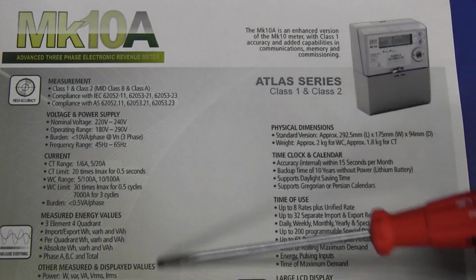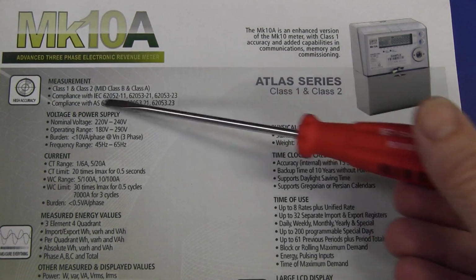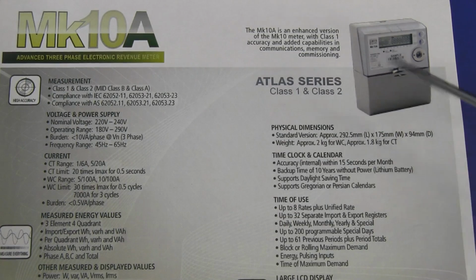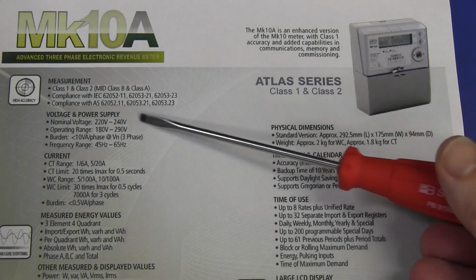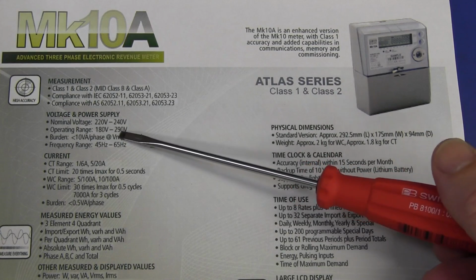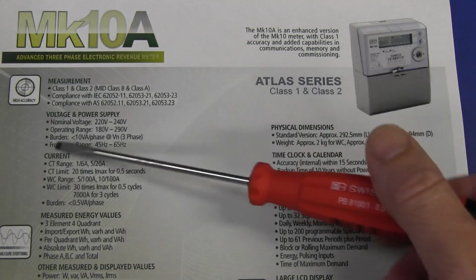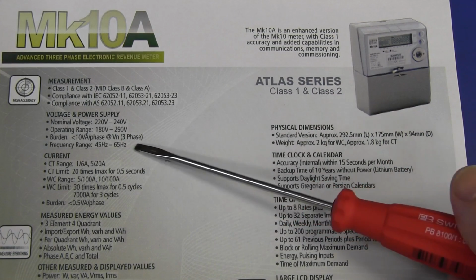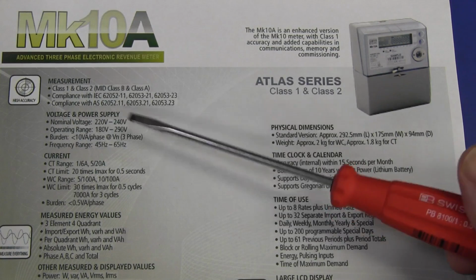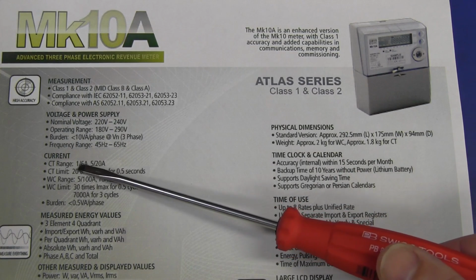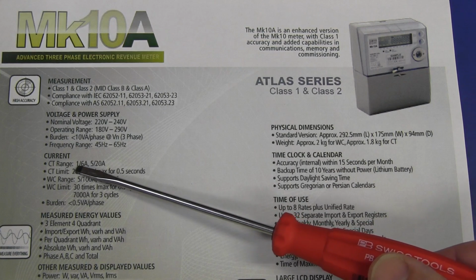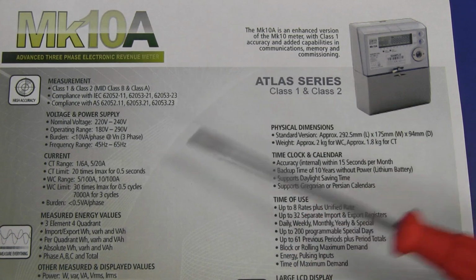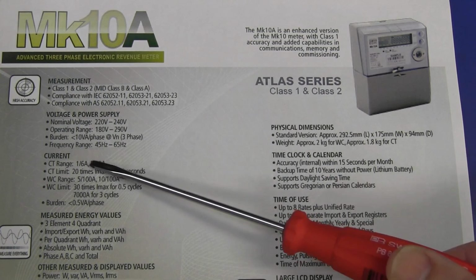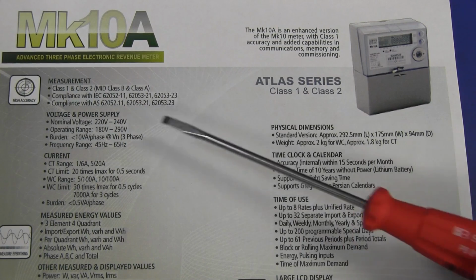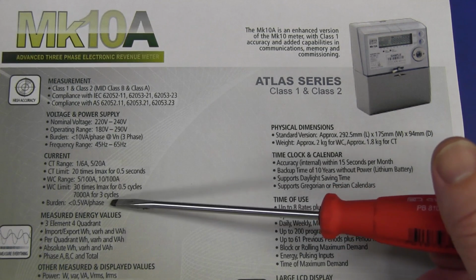I will start out by taking a look just at the spec sheet here, see what we've got. It's all sorts of compliance standards, if you're into that sort of thing, check those out. But it's 220 to 240 volt input, although it does operate from 180 to 290 volts input. Burden voltage less than 10 watts per phase. Frequency range, it operates from 45 hertz to 65 hertz. And then the current range, it looks like one channel 6 amps, 5 channels 20 amps? I don't know. Current limit is 20 times the maximum current range for 0.5 seconds for those surges. Then our burden power in this case, less than 0.5 VA or 0.5 watts per phase.